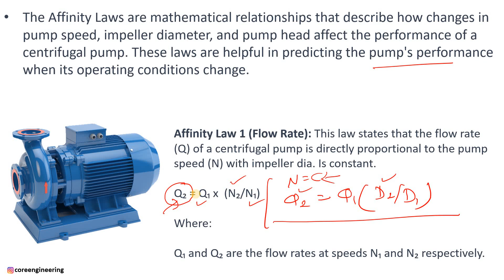So if you increase the diameter, your flow rate will simply increase. Then see the next affinity law, and this is with respect to head, the head developed by the centrifugal pump. If you keep the impeller diameter constant, then what will be the formula? The formula will be this one. H2 is equal to H1 into N2 divided by N1, squared. There, the square comes into the picture. It means that your new head will change 4 times. How? Just see the example.